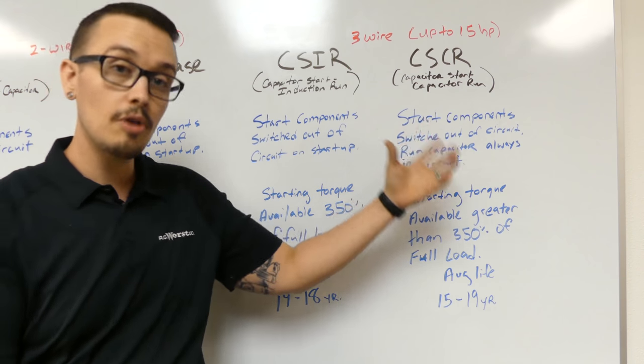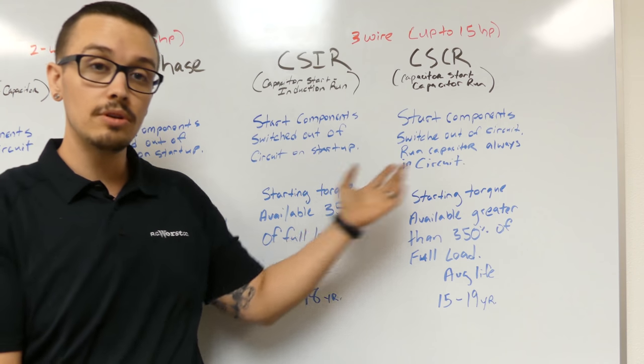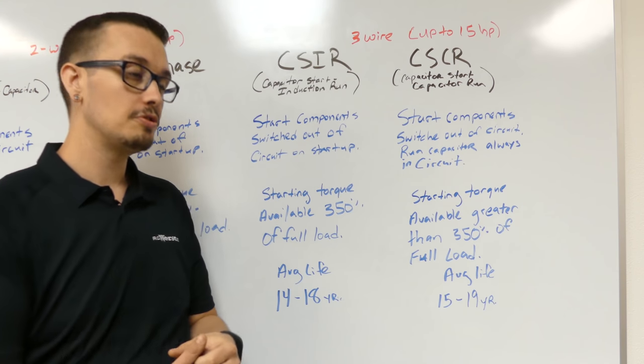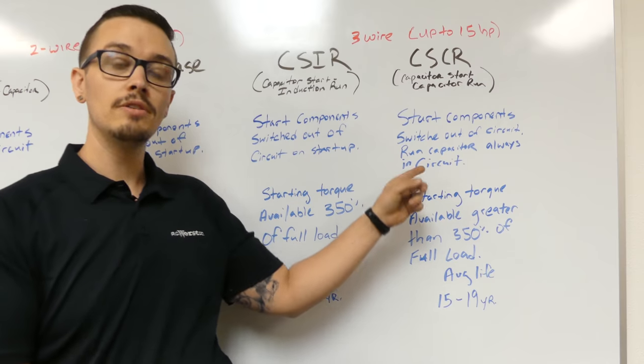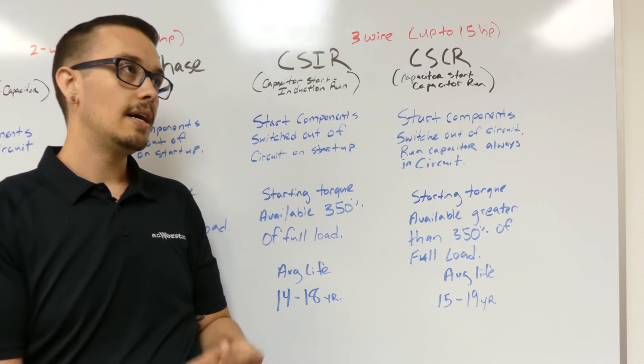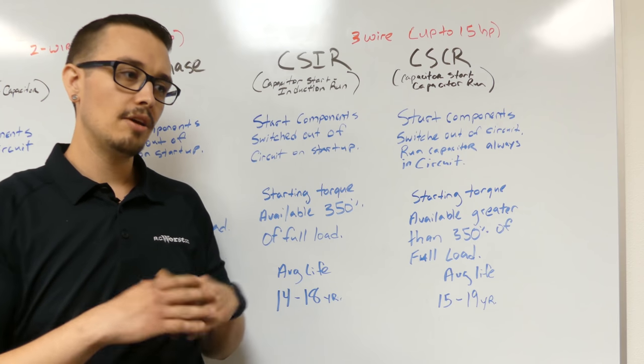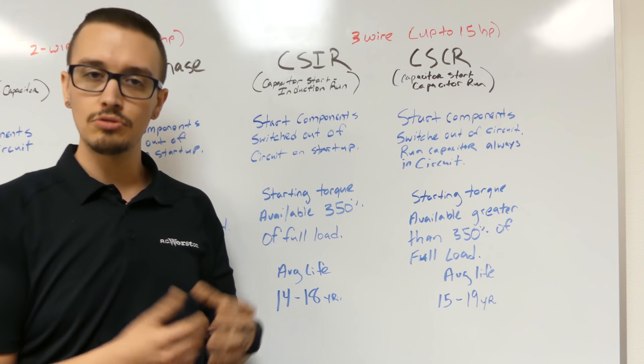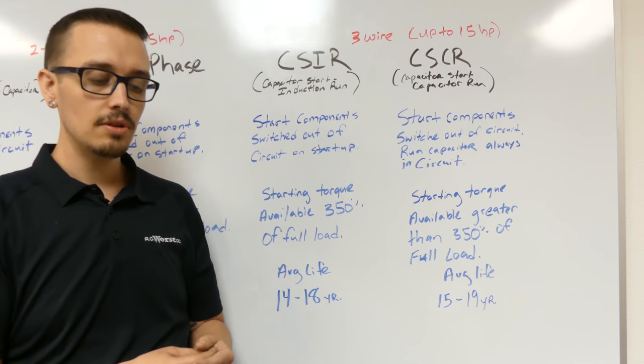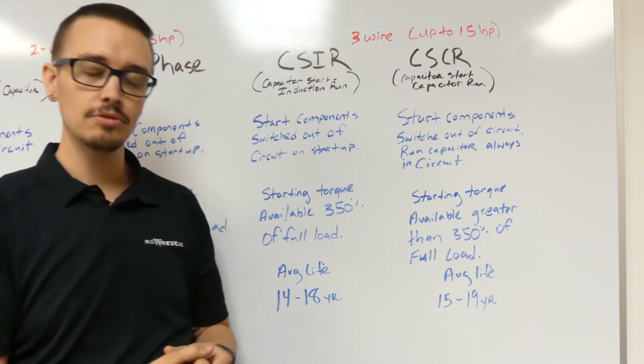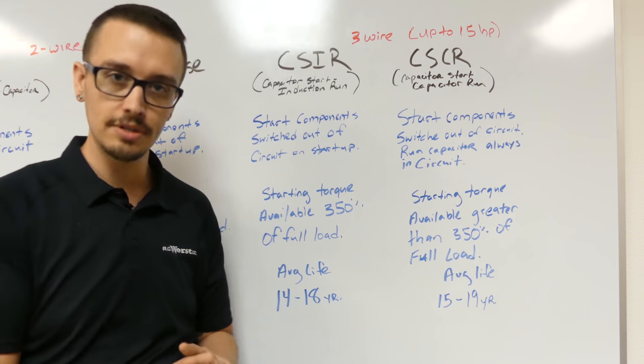With a CSCR panel, the start components do disengage from the circuitry, but there is still a run capacitor that is always engaged from startup. And the whole idea there is that helps to smooth out the load transitions as the load changes around, or the pressure varies, or the flow varies, and so forth.